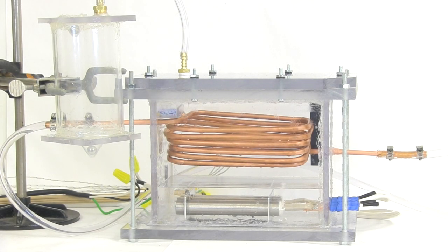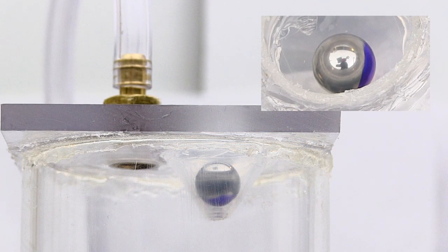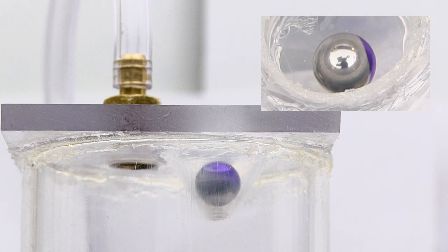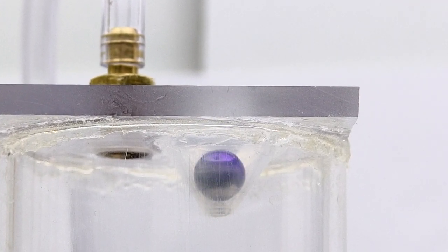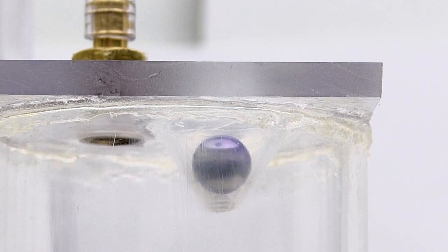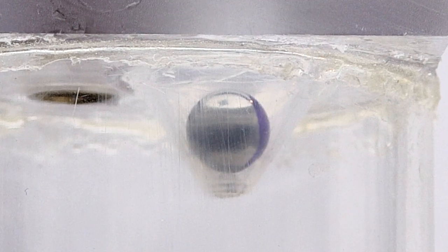The last technique is to use check valves. These valves allow pressure during startup and shutdown to be vented, while containing smaller pressure changes, such as those during power fluctuations. This system uses a simple ball check. The ball is lifted by the pressure inside the container and will spin as the air is released around it, causing losses on startup of about 0.1 to 0.5% of the initial fluid volume. When the pressure stabilizes, the ball settles, sealing the container. This means that no more fluid is lost during operation. The advantage of these valves is that they are very small when compared to the bellows and only allow for fluid loss on startup.